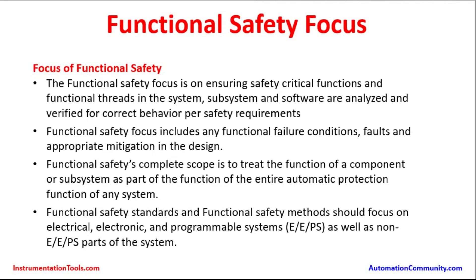Where does functional safety focus? Functional safety focuses on ensuring safety-critical functions and functional threats in the system. Subsystems and software are analyzed and verified for correct behavior per safety requirements. The program software does calculations and gives output commands for the final elements in case any sensor signal goes high or low. Logic solvers work and give output commands. All these systems, subsystems, and software have to be analyzed in functional safety. Functional safety focus includes any functional failure conditions, faults and appropriate mitigation in the design.